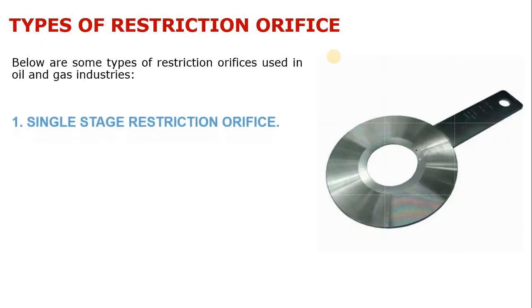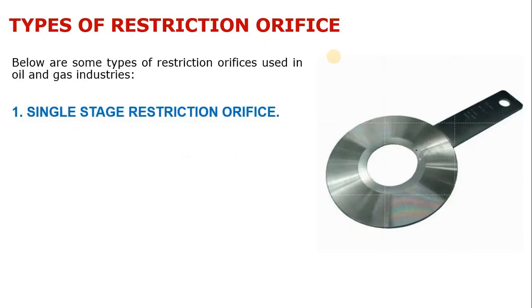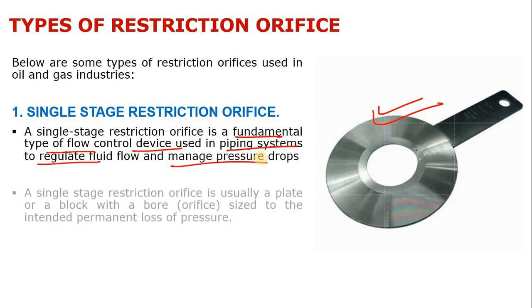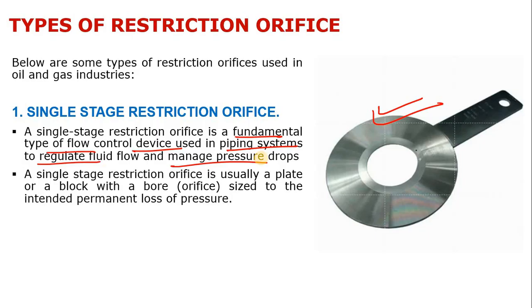There are several types of restriction orifice. The first is the single stage restriction orifice, which has only one stage — one plate with one hole. It is a plate or block with a bore sized to cause an intended permanent loss of pressure. It is installed between pipelines and it is a thick orifice plate, not a thin one, because you have to deal with the pressure.